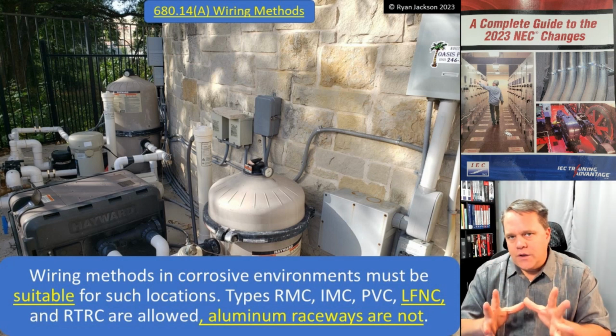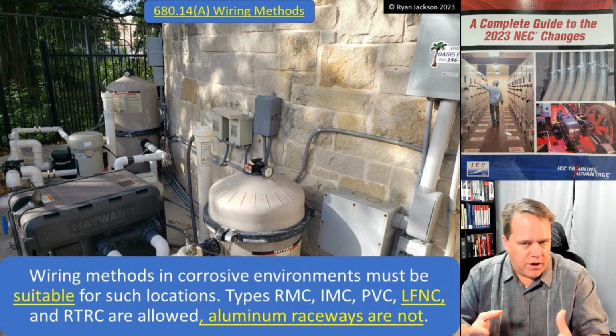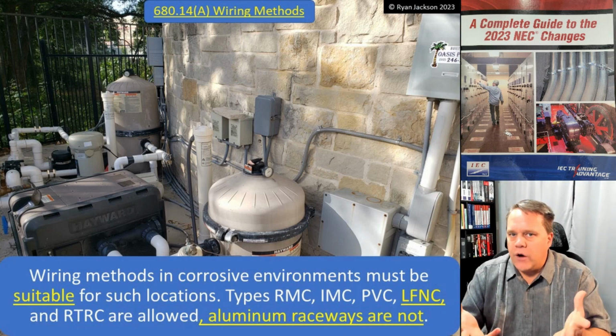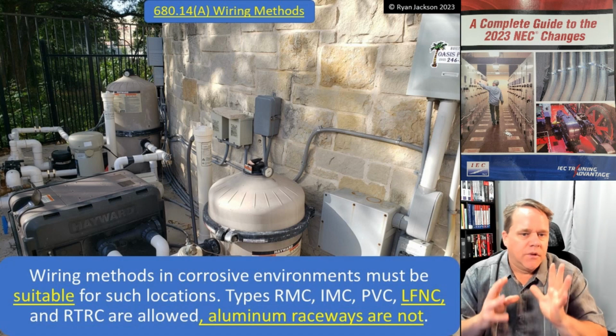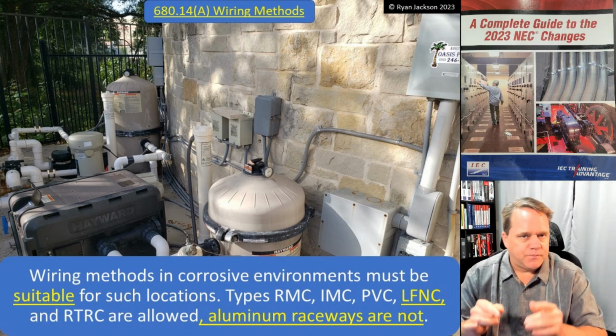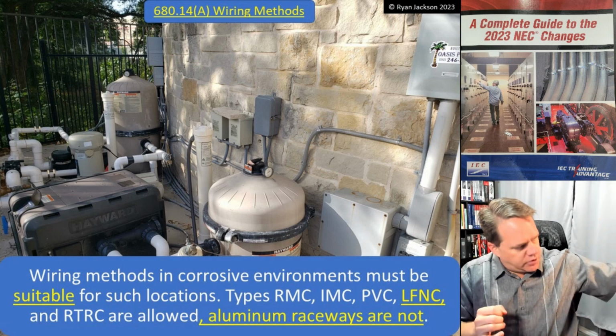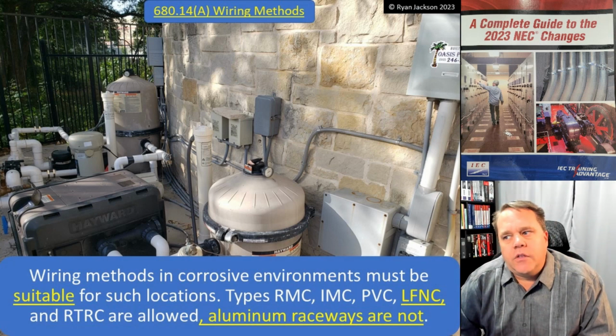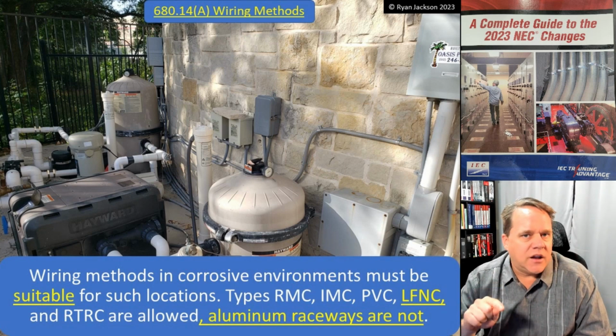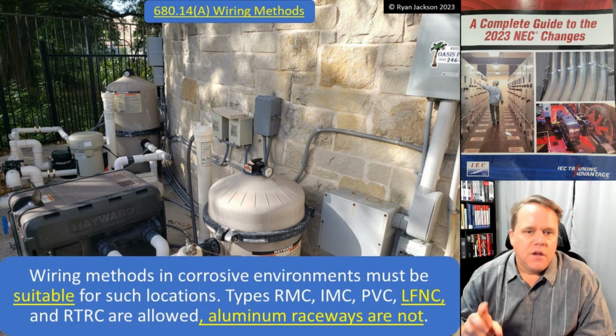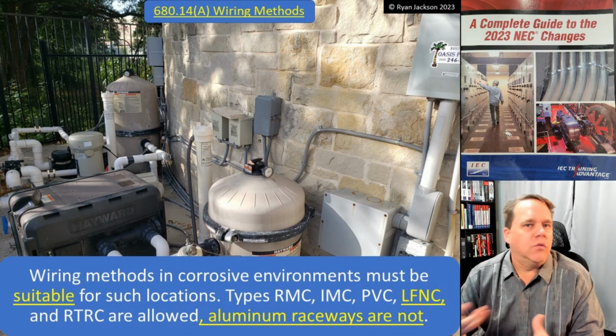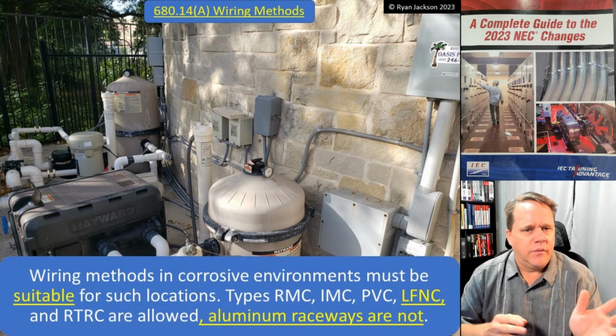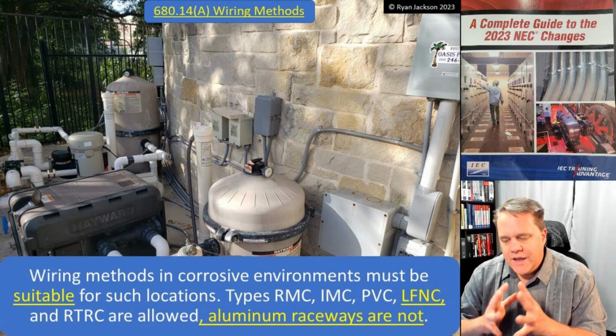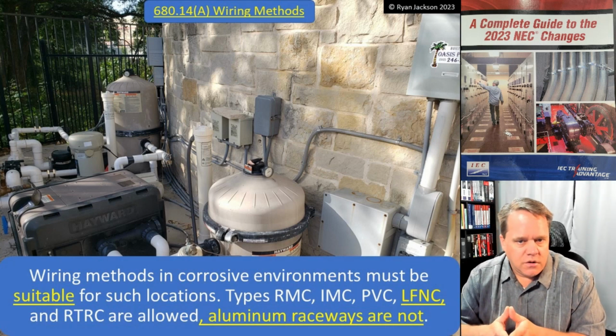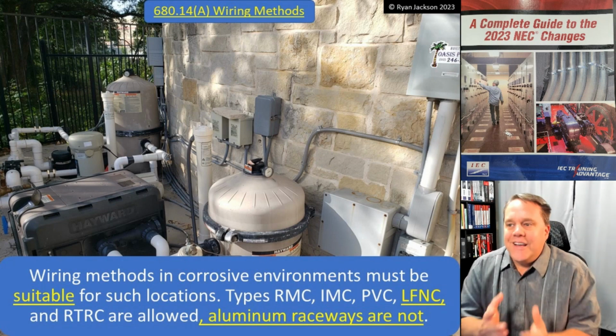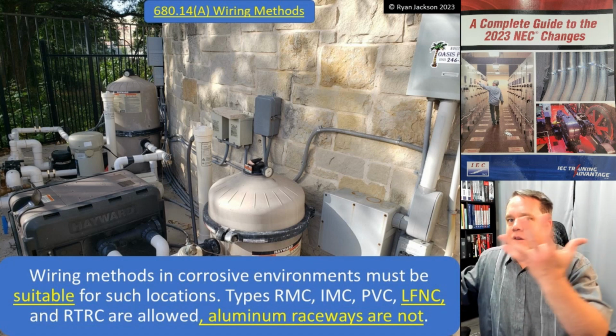I'm showing the swimming pool equipment area. Obviously, it's not a swimming pool equipment room because it's outside, and that's why I want to bring this up. Wiring methods in corrosive environments. What's a corrosive environment? Well, that's where you go back to Article 100, and you're going to find out that it's an area that does not have adequate ventilation and contains swimming pool chemicals like chlorine and what have you. Go back to the Article 100 definition, you'll see what I'm saying. But here's where I'm going with this. Areas that do not have adequate ventilation. Well, this is outside. It doesn't get more ventilated than being outside.